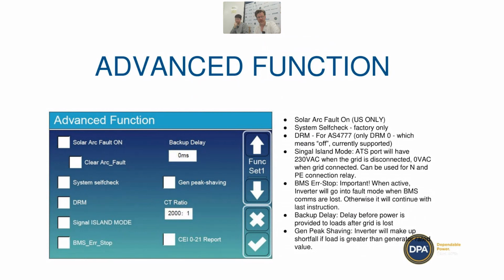Then if you're doing managed batteries, you also need to turn BMS error stop on, which is here in the bottom left-hand corner - you see BMS error stop. What that does is that if it stops receiving commands from the battery, it ceases functioning instead of just continuing on with whatever the last command is. I don't know why you'd actually want this as an option, but you need to turn that on. The rest of these you can leave as standard, which is off.